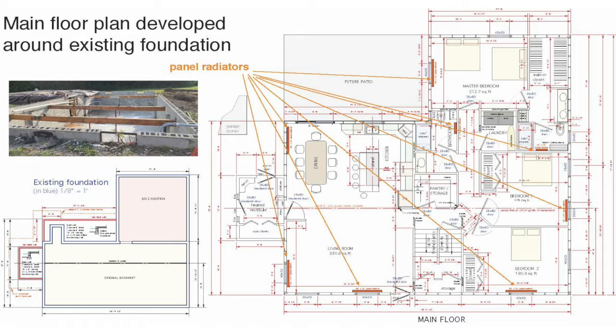Now we use panel radiators, and those orange rectangles are where we put the panel radiators. We sized these panel radiators around an average water temperature of 110 degrees. We actually found that we can run them quite a bit lower than that and still get the output that we need, but we sized them around an average water temperature of 110. And again, where did that come from? This morning I mentioned my own criteria. I try to encourage anybody designing modern systems today to keep the water temperature at design load no higher than 120, lower if possible. So you're well within the realm of how heat pumps, as well as modulating condensing boilers, or if you want to add solar thermal, all those heat sources are going to operate better at these lower water temperatures.